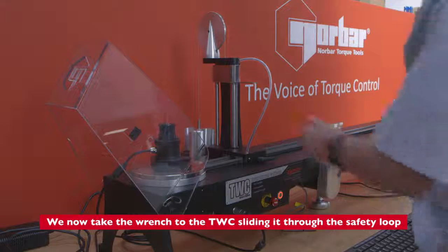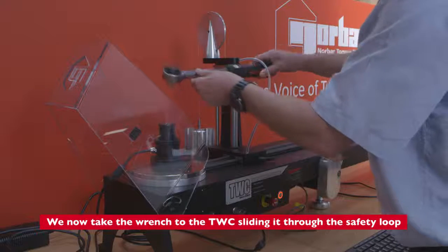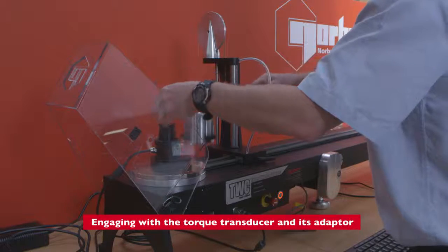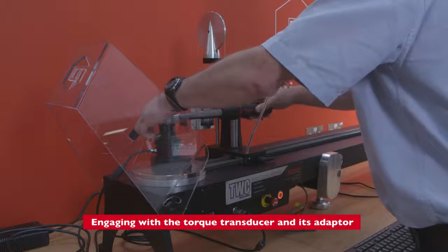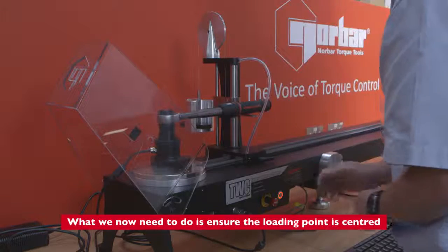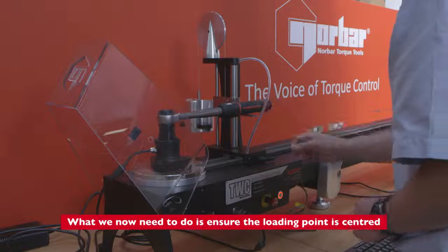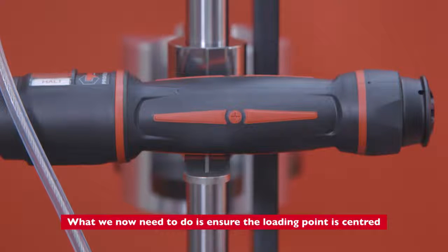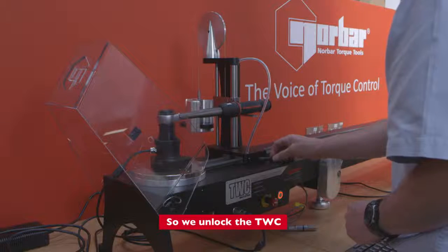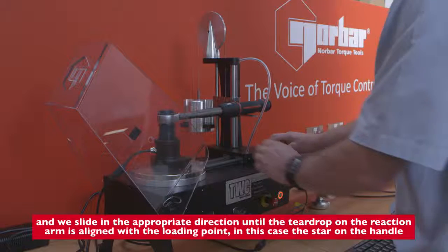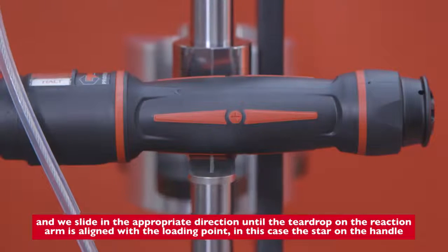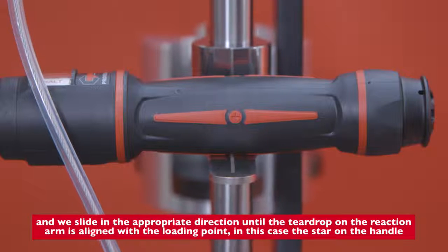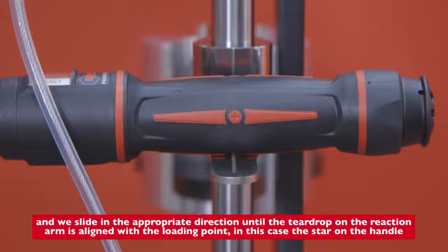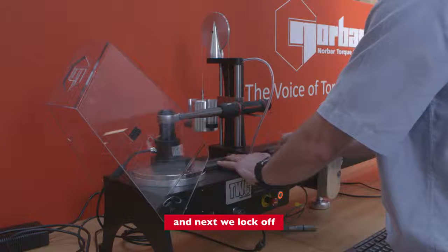We now take the wrench to the TWC, sliding it through the safety loop, engaging with the torque transducer and its adapter. What we now need to do is ensure the loading point is centered. So we unlock the TWC, and we slide in the appropriate direction until the teardrop on the reaction arm is aligned with the loading point, in this case the star on the handle. And next we lock off.